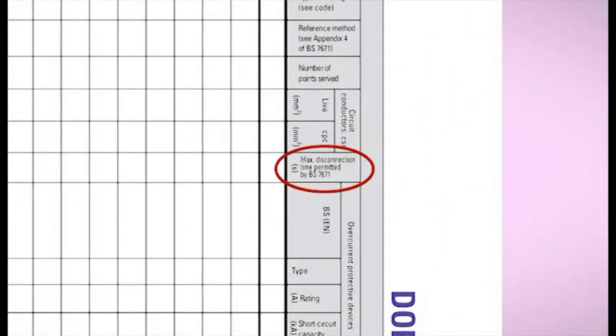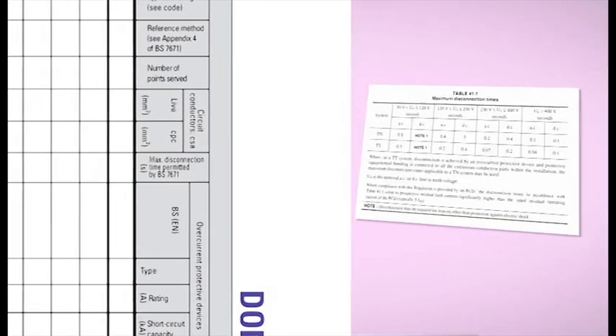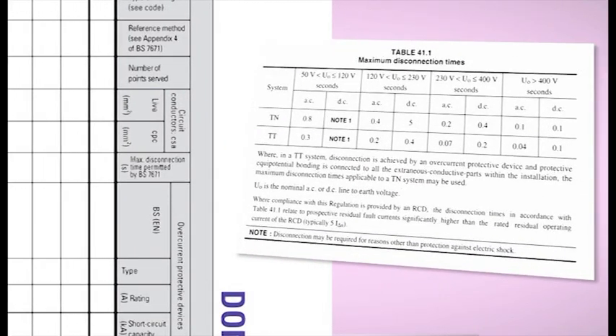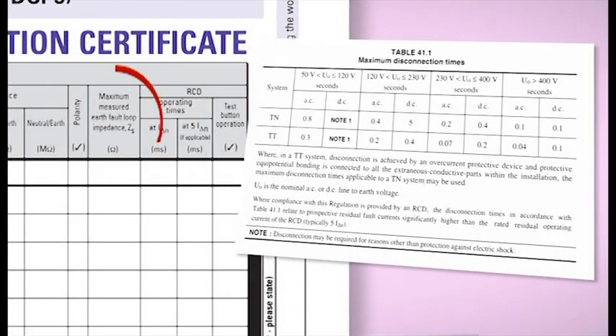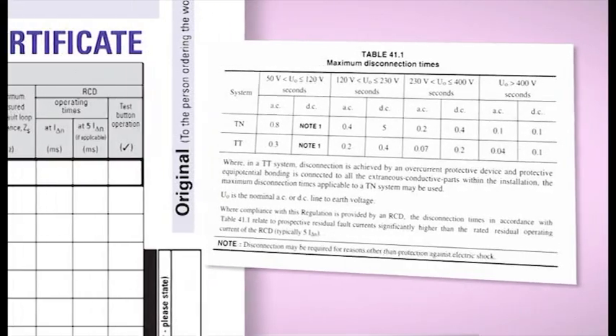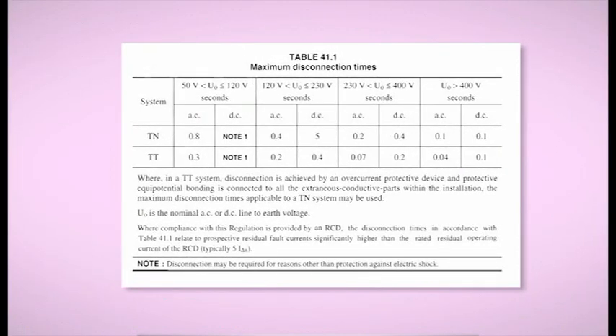The next column is titled Maximum Disconnection Time Permitted by BS 7671. This is the value determined by the designer from the relevant table in Chapter 41 of the regs, and is information that we need to cross-reference later with the ZS test results. You will see from Table 41.1 that for circuits not exceeding 32 amps on a TN system, the maximum disconnection time is 0.4 of a second. For a TT system, the maximum disconnection time is 0.2 of a second.